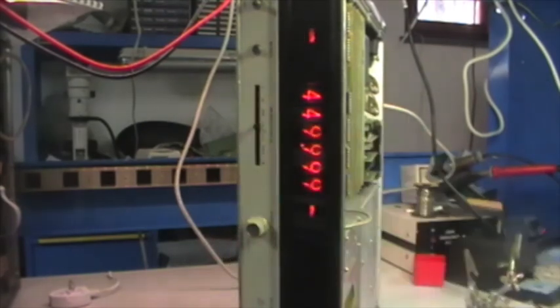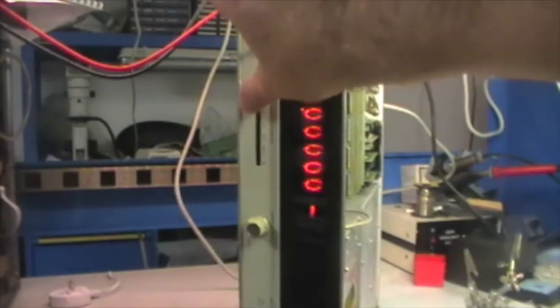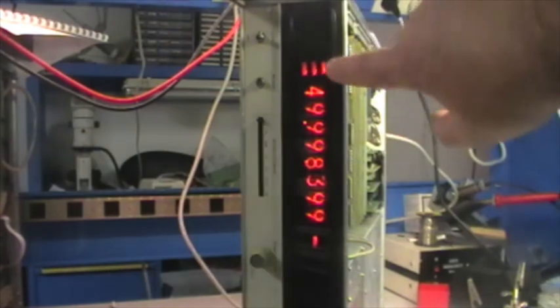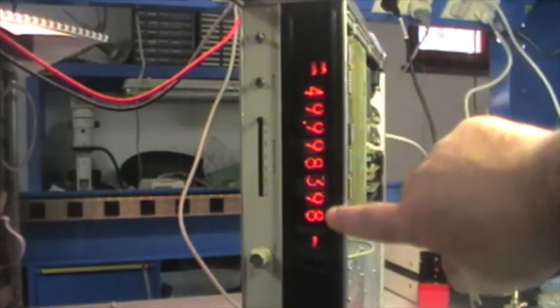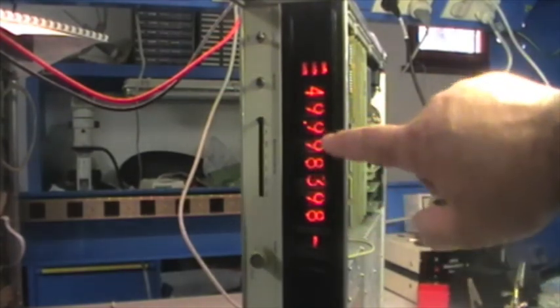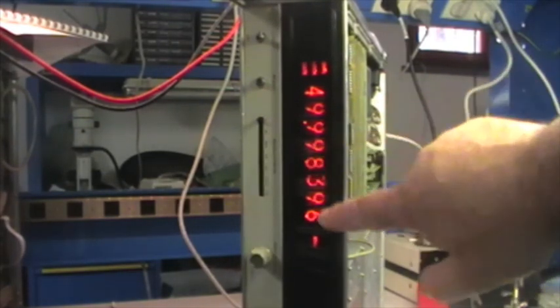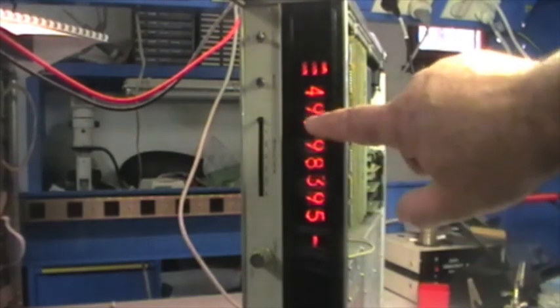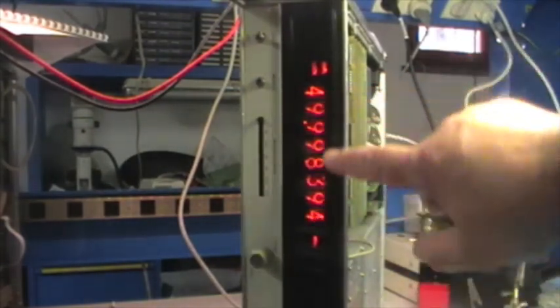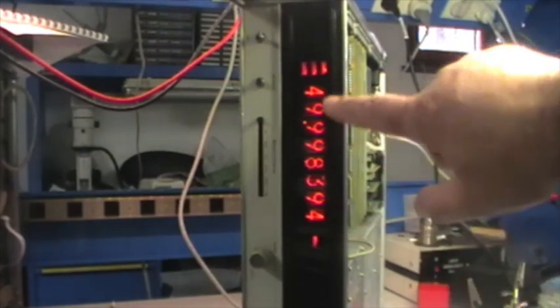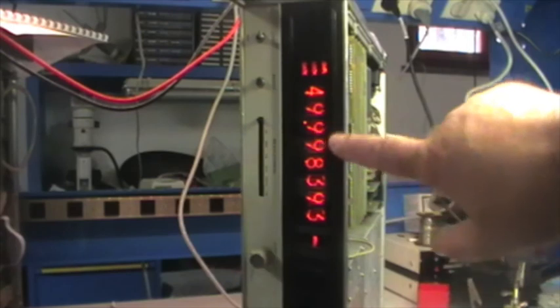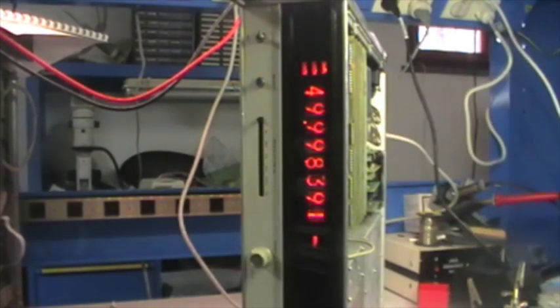So the replacement of the chip fixed the problem. So for sure we need a calibration. Let's see, in this range it should say overflow. That is correct. And this is the full count. So we have 1, 2, 3, 4, 5, 6 digits after the comma. So we need a calibration at this point, I believe. But at least now it's counting correctly. So the troubleshooting was correct as well, and the chip was faulty. So really happy for the moment.